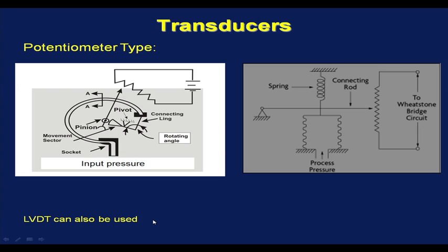We can also use a linear variable differential transformer or LVDT to convert these to a transducer that gives us an electrical signal. Because we have seen in our previous lectures that LVDT is a distance measuring transducer. So, the deflection of this pointer or connecting rod can also be converted to an electrical signal by using LVDT.